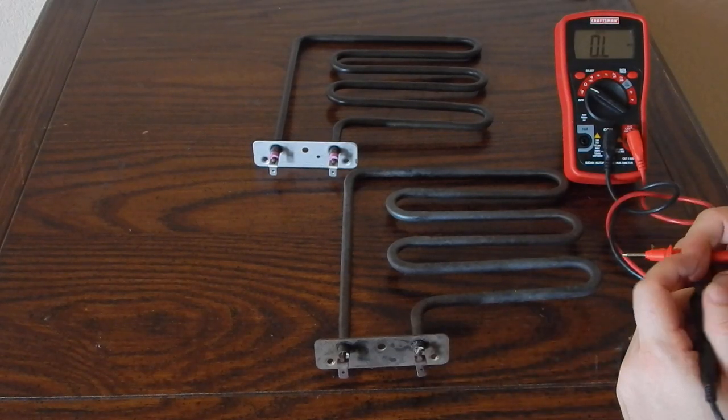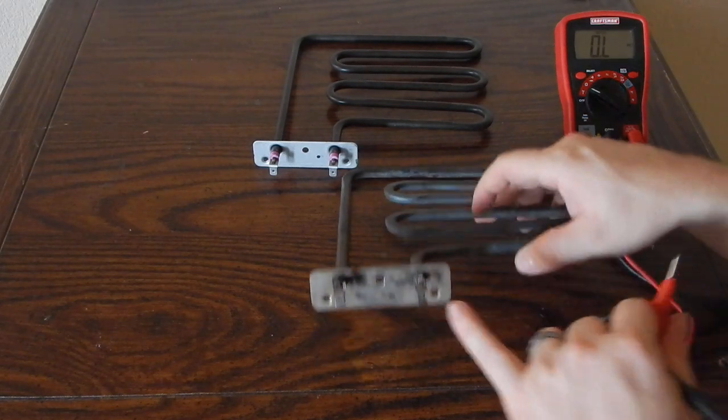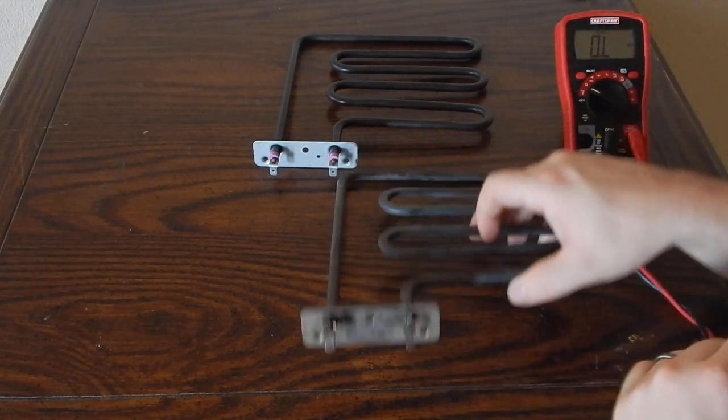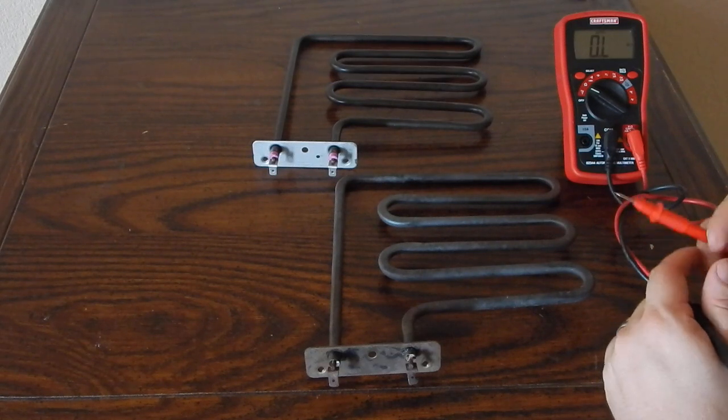That's why this one was tripping the GFI breaker. Normally the ground wire screws in right there. So that's what tripped it up.